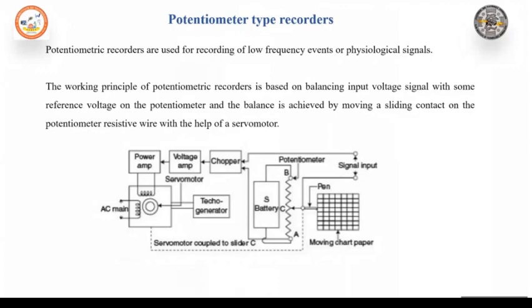This is accomplished by a marking device fitted on the pointer, under which moves a motor-driven chart for recording. The block diagram of the self-balancing potentiometer that I have shown illustrates how a servo motor and other control devices balance the potentiometer. In this circuit, the voltage signal under measurement is applied to one input terminal of a device called the error detector, and another adjustable reference voltage signal VR is applied to the second input terminal of the error detector. The error detector compares the two signals and gives the result at the output terminal.